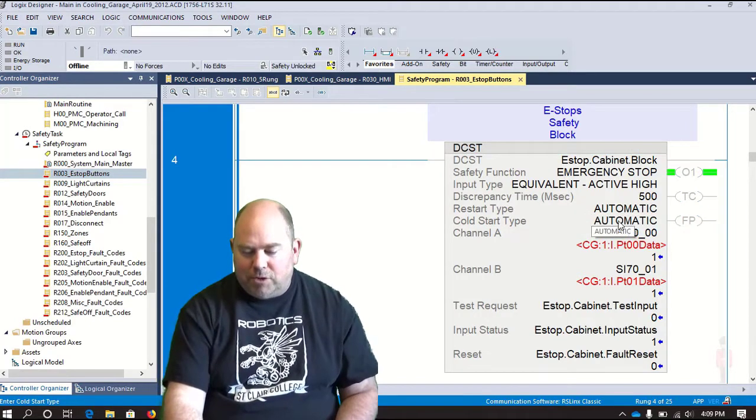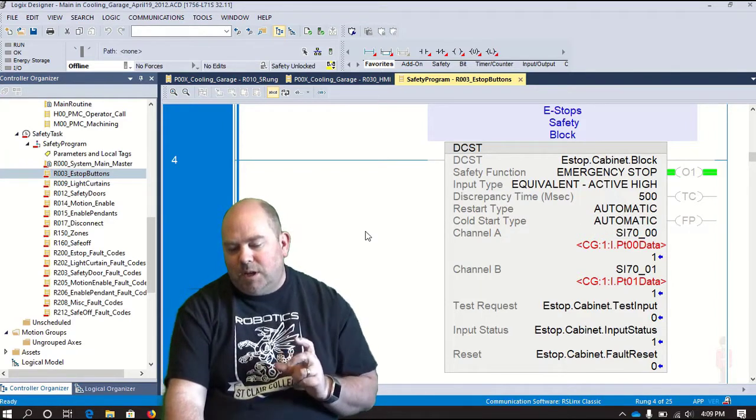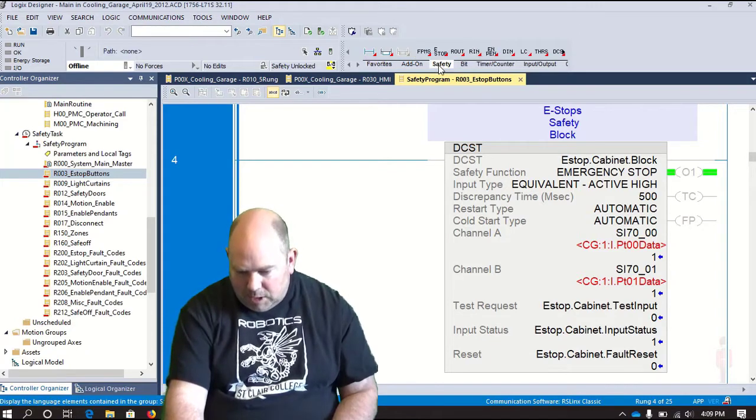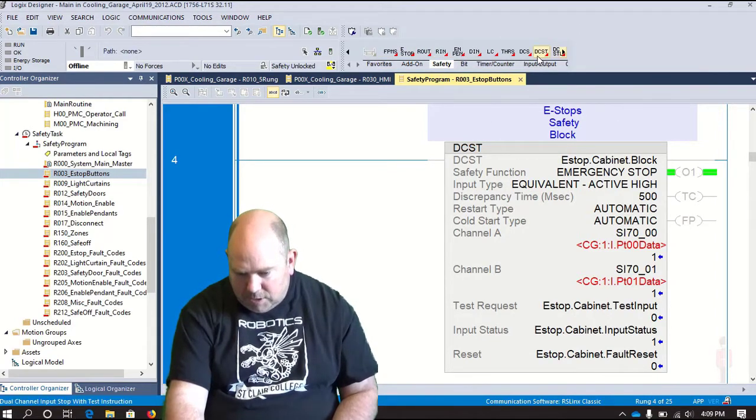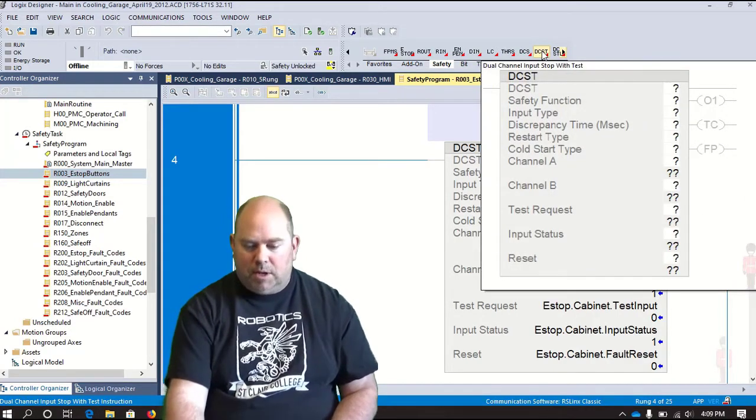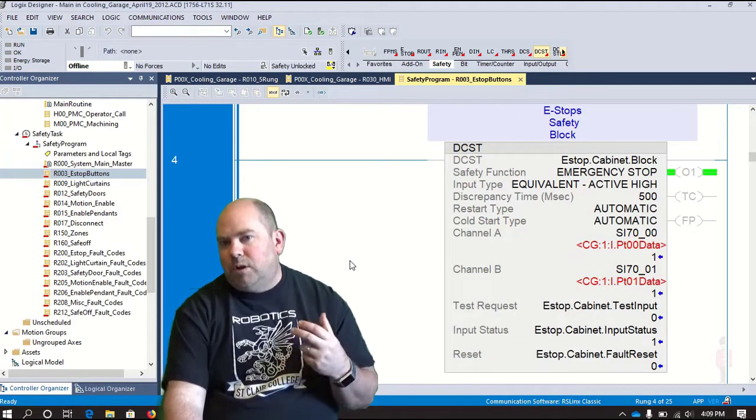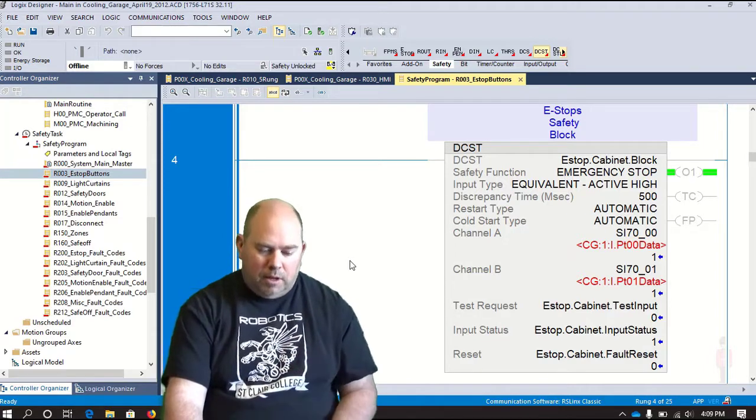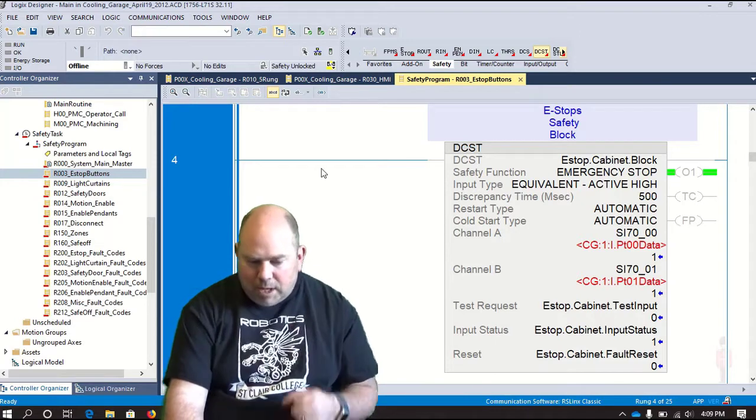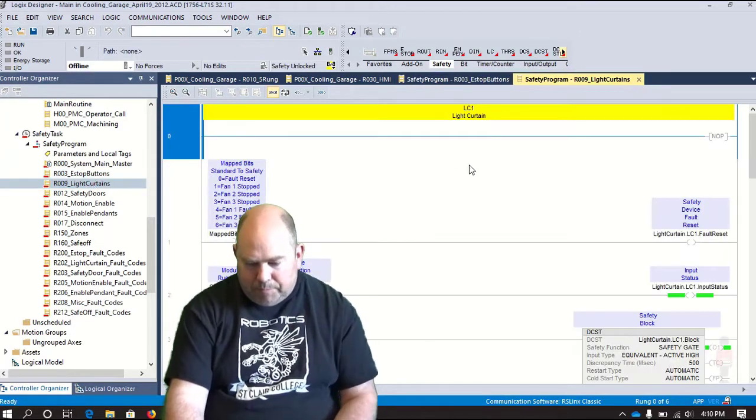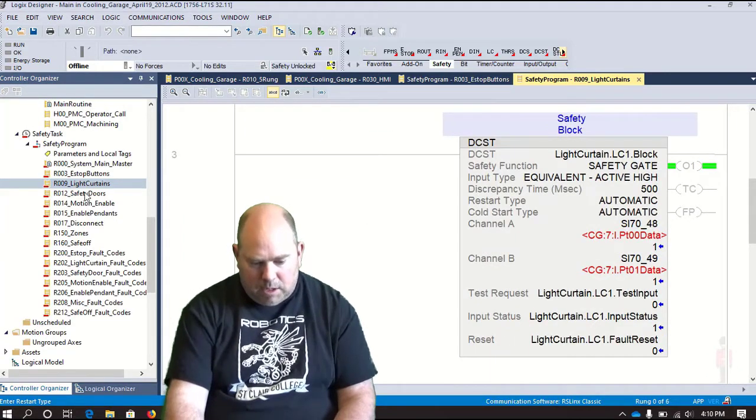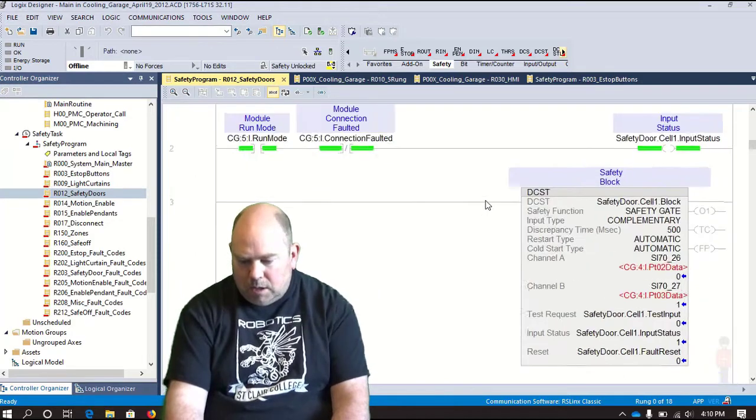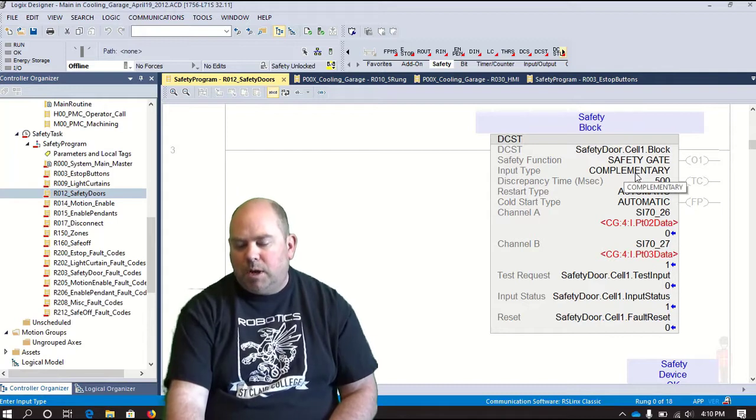So this we have it just as automatic, so it'll just come up in the on state. So this is the DCST block. So that is one of the blocks, if you look up here under safety, DCST, dual channel input stop with test. Okay, so that's one of the more advanced type blocks. And the other thing we liked about this one, it's very good to get a lot of different fault codes out of it. I think this is one of the reasons why we like using this one as well. But we're using that same block for e-stops, using it for the light curtains as well. Using it for our safety doors. You can see for the safety doors, that actually used a complementary input type.